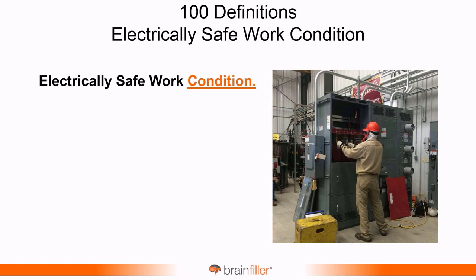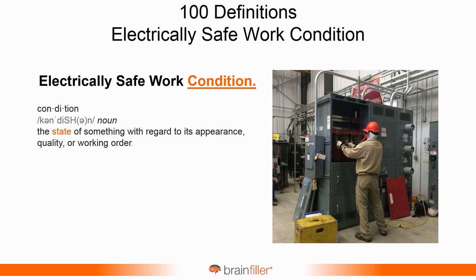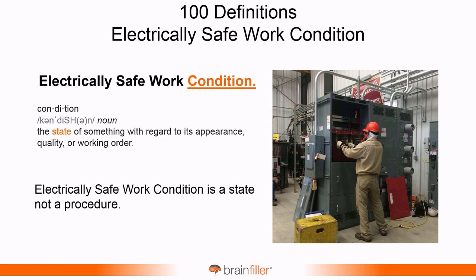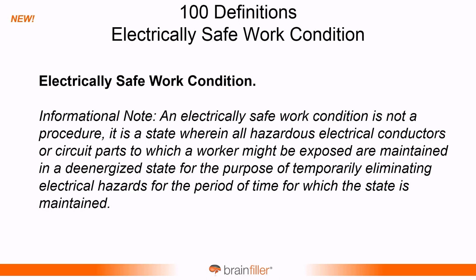So to introduce this, I thought, well, let me consult the dictionary of all places. Let's take a look at what the word condition means. It's a state of something. And that is exactly what the clarification was all about, that the electrically safe work condition, it's a state. It's not a procedure. Yes, there is a procedure, but that's later on in NFPA 70E. So because of this, there was an informational note added, and the informational note clarifies this by stating that an electrically safe work condition is not a procedure. It's the condition. It's a state wherein all hazardous electrical conductors or circuit parts to which a worker might be exposed, and you could read the rest of it. But this is all about just the actual state. Now, to establish the state, yes, there is a procedure for that we see later on in NFPA 70E.